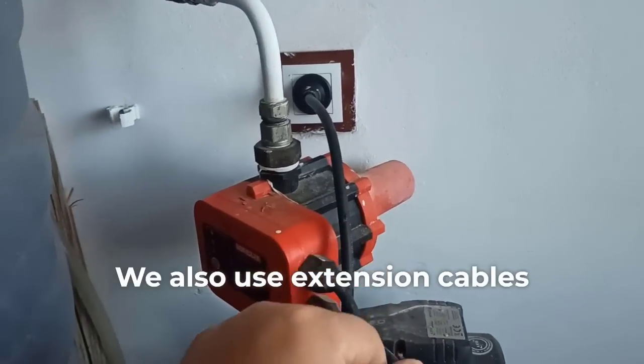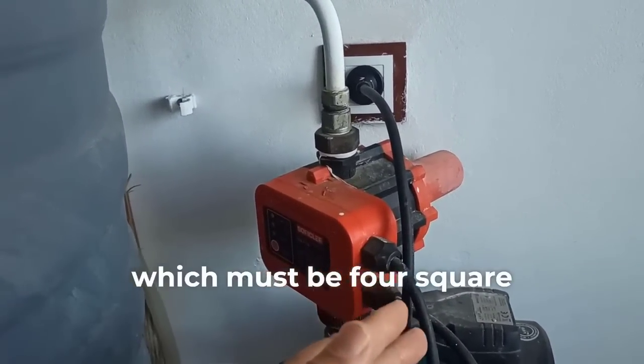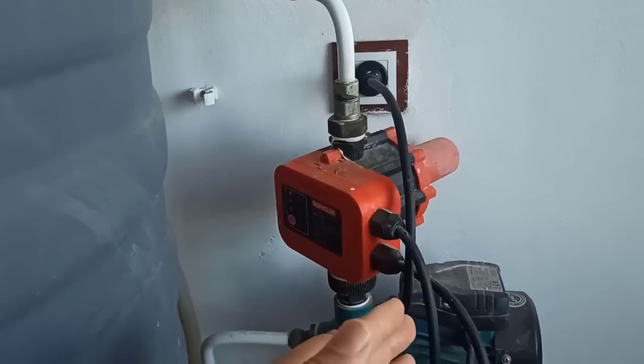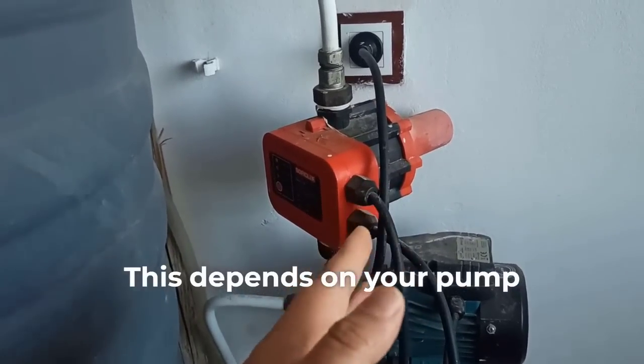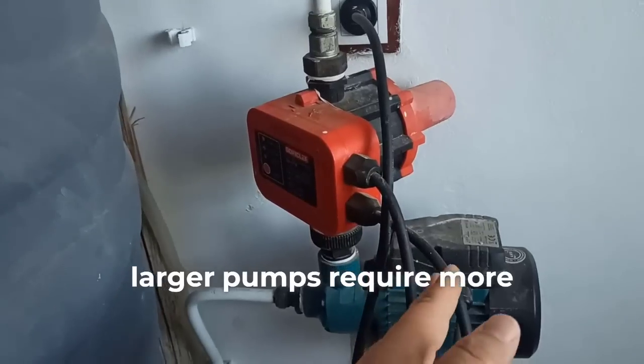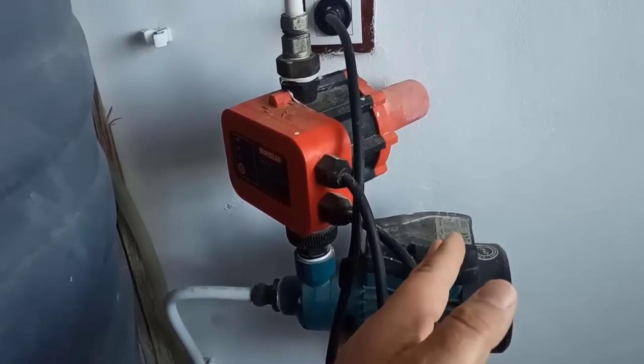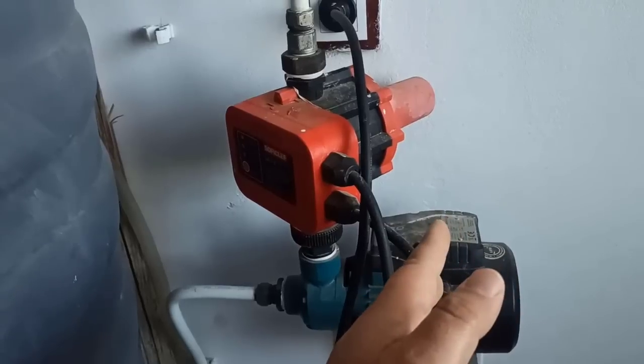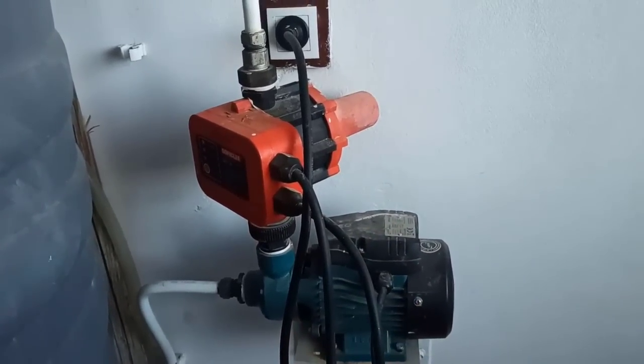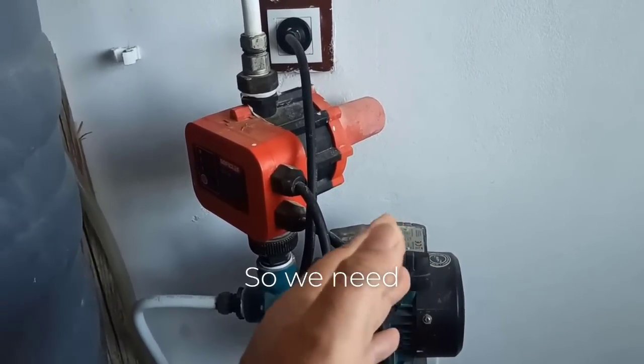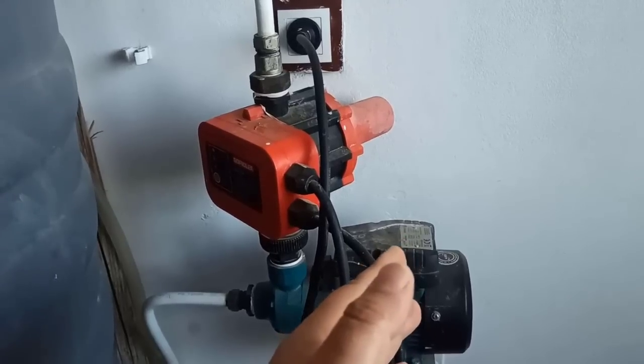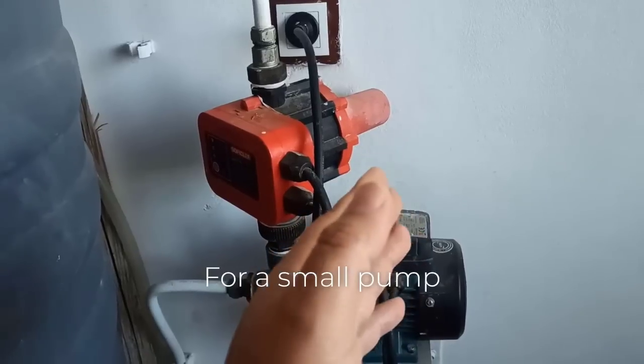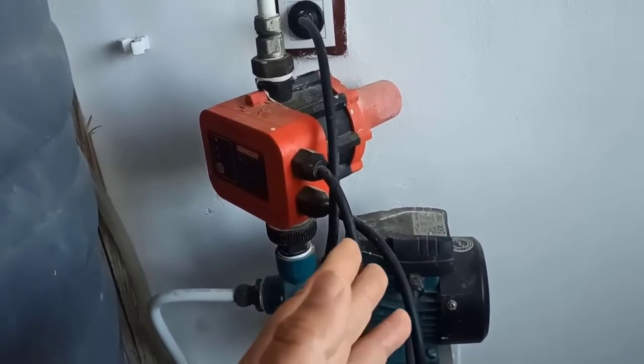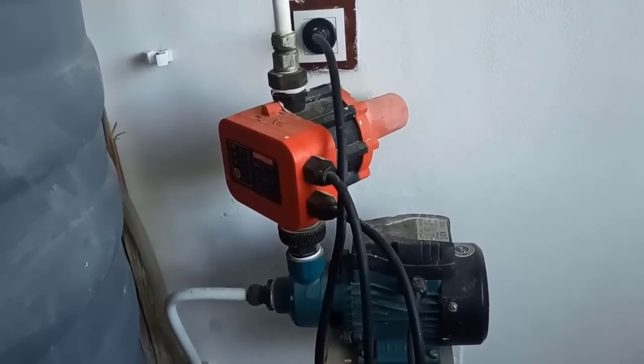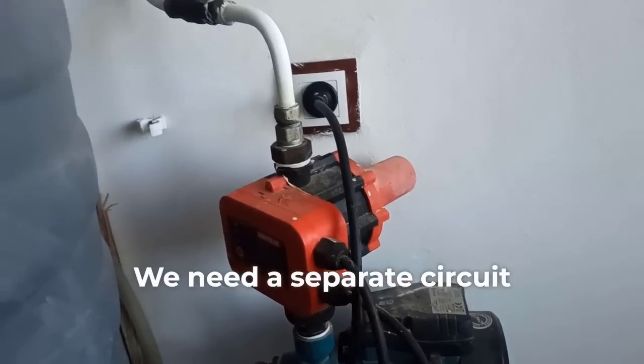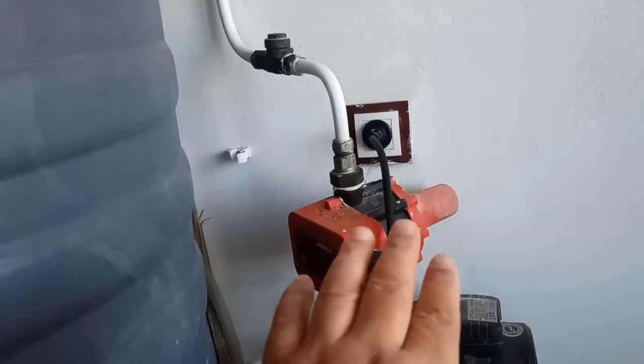We also use extension cables or wires which must be 4 square millimeters thick. This depends on your pump size. Larger pumps require more electrical current or a higher load. So we need 4 mm wire. For a small pump, you can use 2.5 mm wire. This is for the electrical outlet. We need a separate circuit breaker just for this pump.